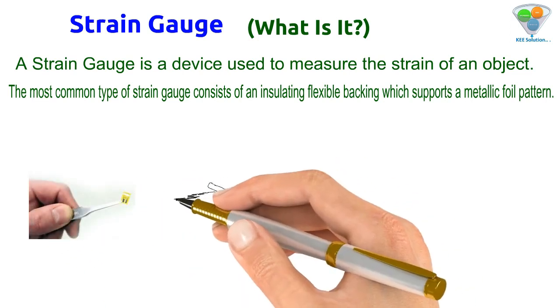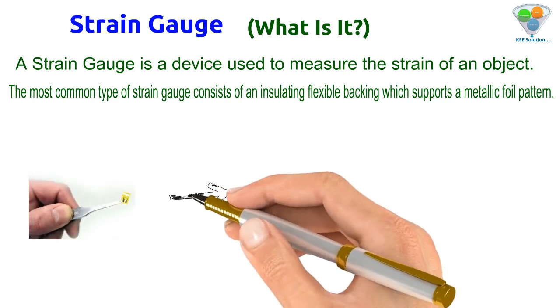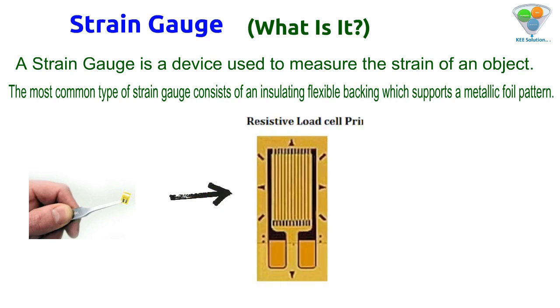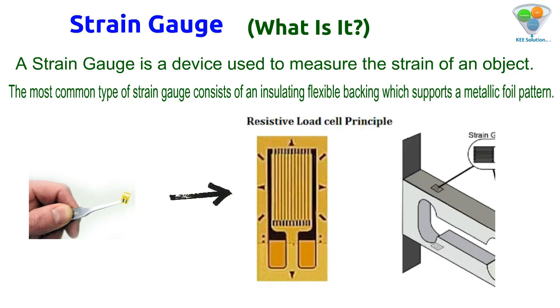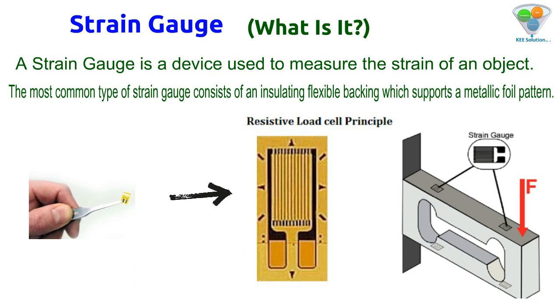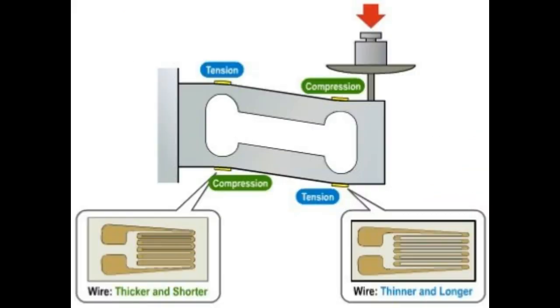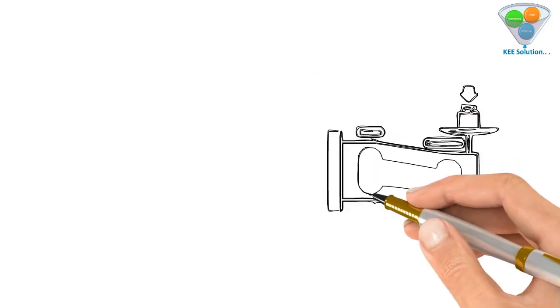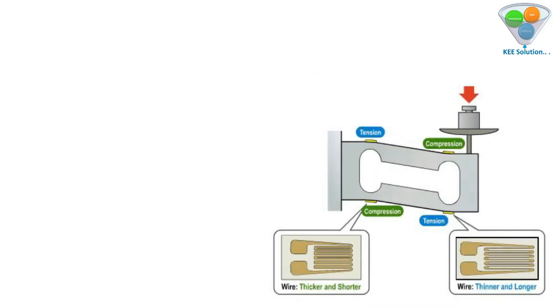On the right side you can see a load cell which has four strain gauges. When force is applied, the gauges compress or expand, causing a resistance change in the strain gauges, and that is measured in the form of voltage by a bridge.